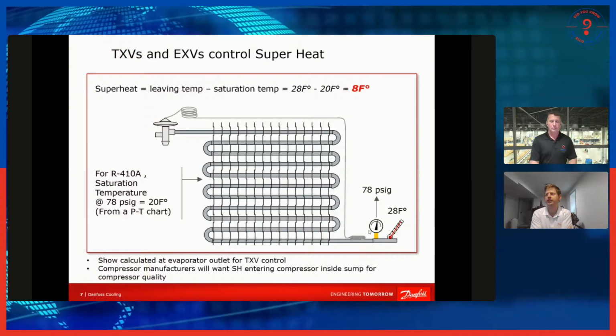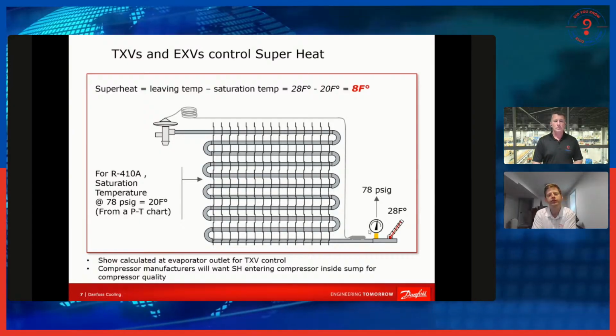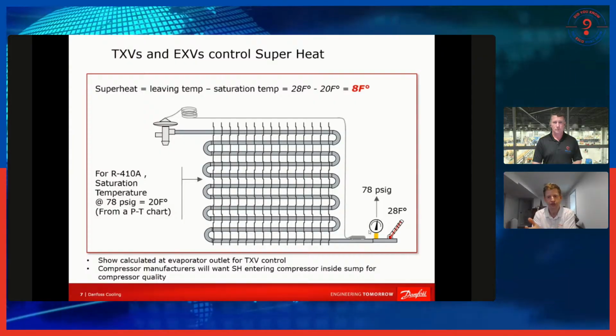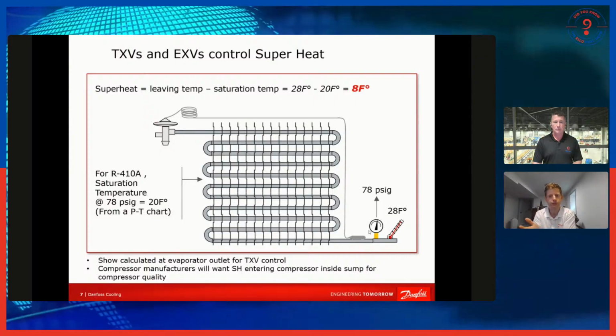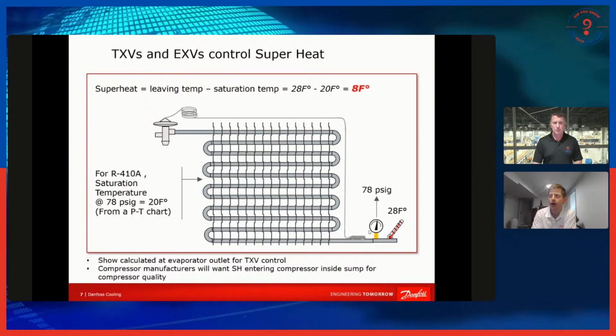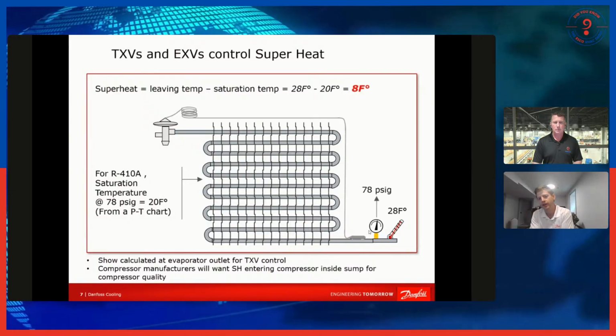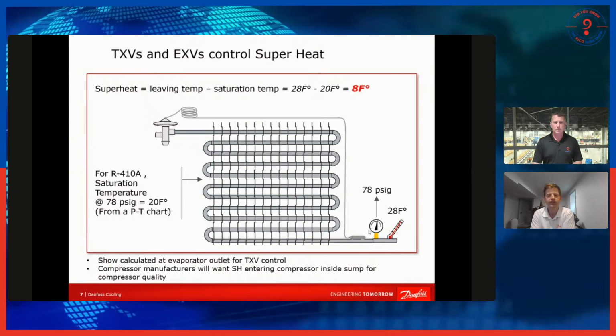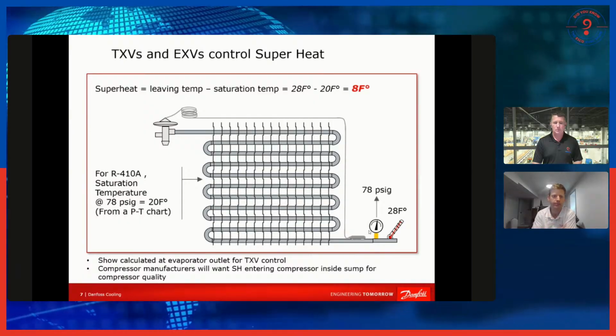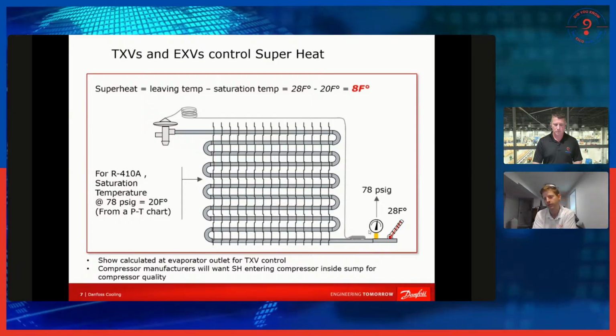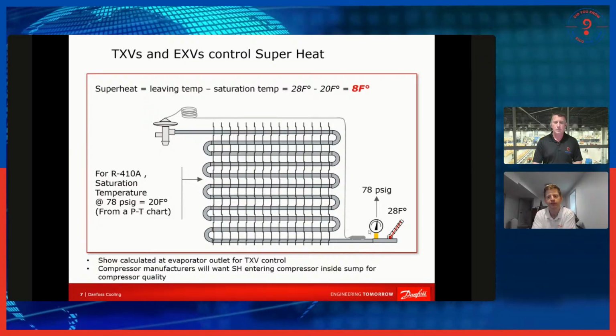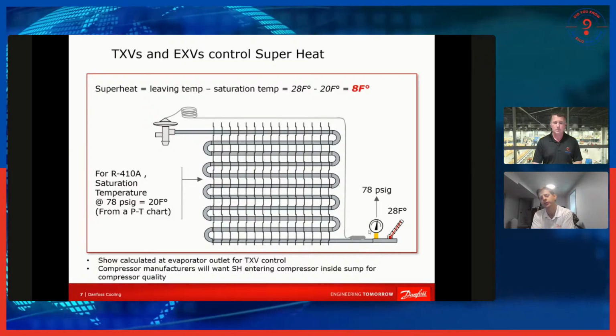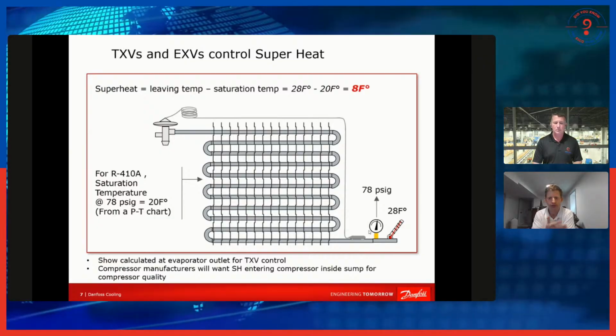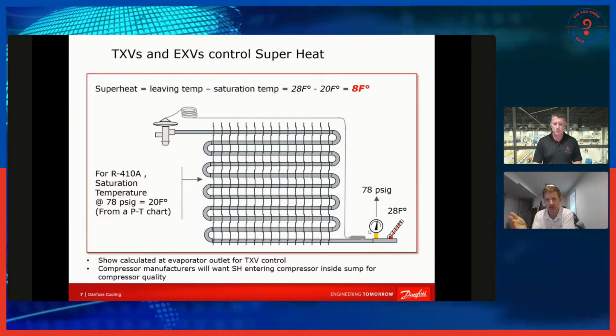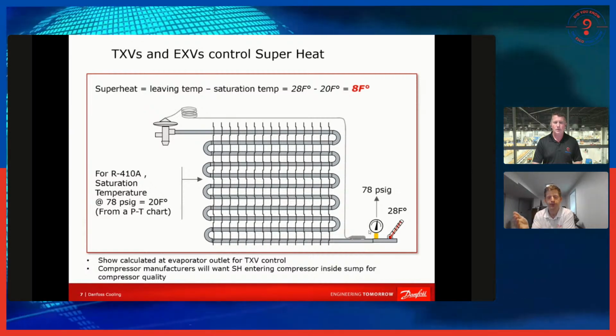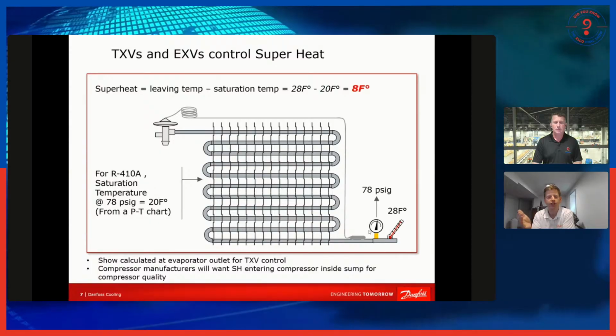And I think a good thing to also consider is, if you have an EXV, where's the pressure transducer at? And when you've got a TXV, where's the external equalizer at? Because generally it's supposed to go right at the outlet of an evaporator, but you might sometimes see manufacturers put it after the 4-way valve before the compressor. And that's also a fair way to do things, because you're now trying to protect the compressor by controlling superheat coming back to it. It just kind of depends.